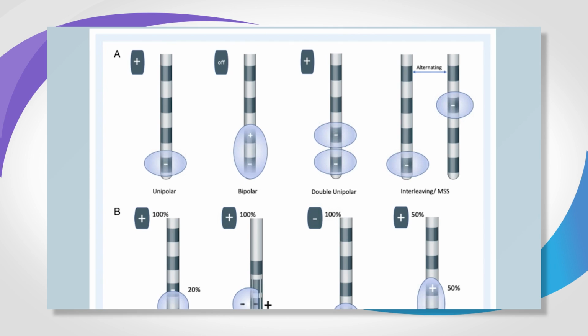So this is a large field of energy. It's called unipolar or monopolar. Next to it is bipolar, where the negative, or cathode, is set on the electrode, and adjacent to it is the positive, or anode. And so it's a smaller field of energy. It's closer to the electrode itself, and that is many times used when we have side effects from monopolar stimulation. We can also use more than one contact at the same time, so you can have double, triple, or quadruple monopolar. Unipolar or monopolar means that the case is positive.